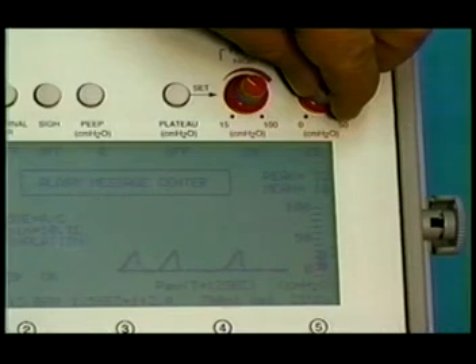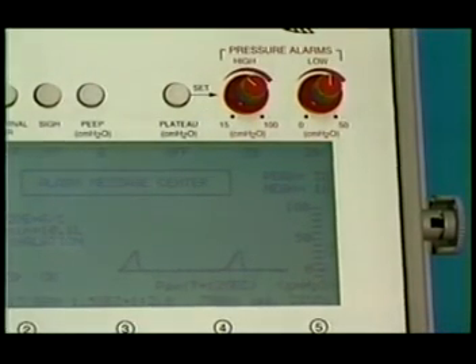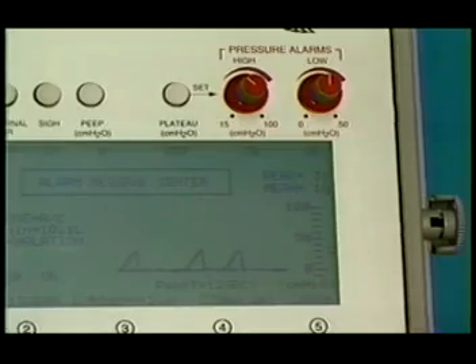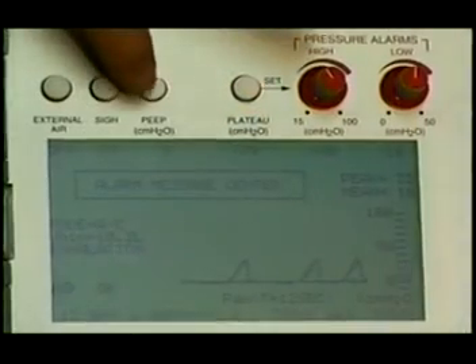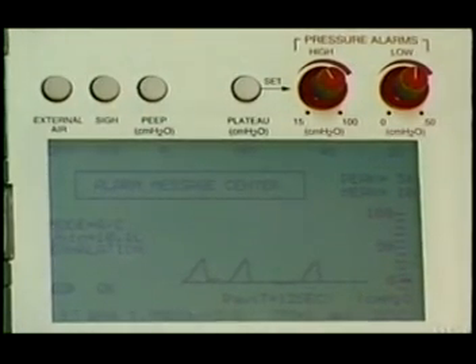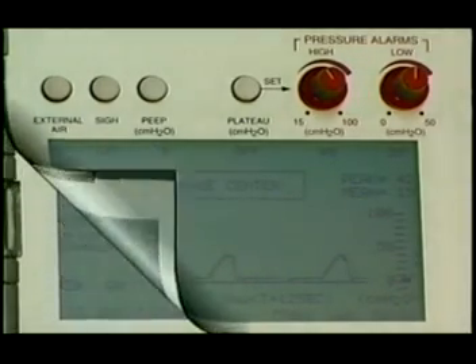The low airway pressure alarm set point indicator shows the current setting of the low pressure alarm control. It is displayed adjacent to the digital bar graph. The PEEP off-on set push-button switch adjusts the internally generated PEEP set point. Its default value is off and increases by 1 centimeter of water each time the push button is pressed. Its range is from 0 to 20 centimeters of water, and the set value is displayed in the LCD beneath the push button switch.